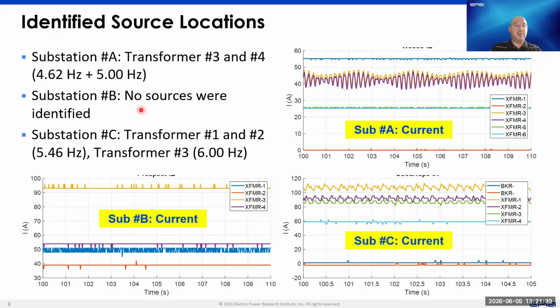So that was very helpful to basically narrow down and see exactly which are the sources of those oscillation modes. Specifically for substation A, we were able to observe those oscillations in the measurements from two transformers, transformer 3 and transformer 4. And in this case, we could see the 4.62 and the 5 hertz oscillations.